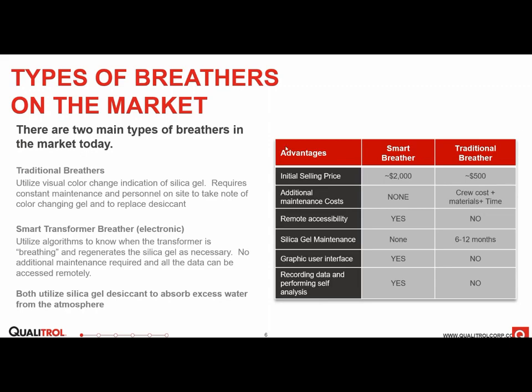Some of the advantages of a smart breather is that it requires no maintenance over time. So you eliminate the need to send a crew out to the field and replace the silica. You can remotely access it to look at things like the RH of the silica, the temperature, the regen cycle, anything like that. It can also data log, so you can see how many times it regenerates, how much your transformer is breathing, and things like that. You can trend your transformer's operation over time through the breather's operation.